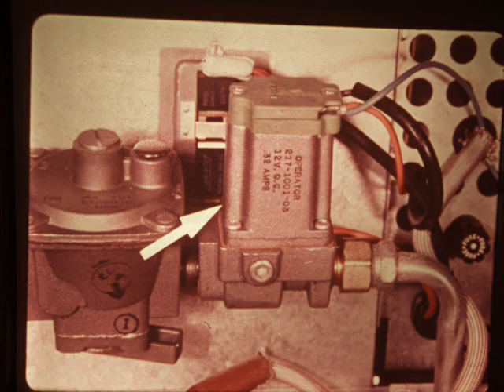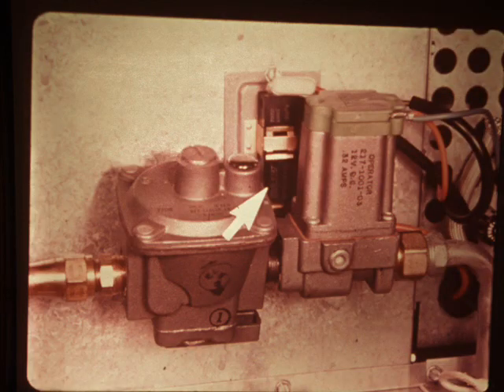The gas solenoid valve controls gas flow to the combustion chamber. It opens and closes in response to the thermostat. The limit switch is a safety device. If the furnace gets too hot, over 200 degrees, it opens the electrical circuit to the solenoid valve, thereby shutting off the gas to the burners.